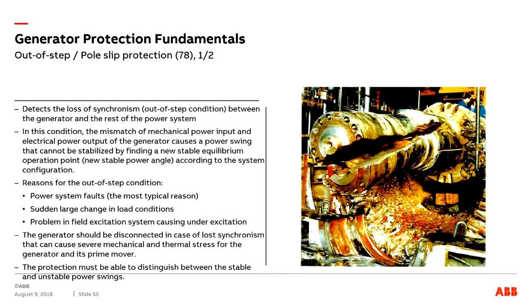The reason for an out of step condition could be power system faults, sudden large change in load conditions, or a problem in the field excitation system causing under excitation. Okay, the protection must be able to distinguish between stable and unstable power swings, which is important because there could be power swings in the system, and we should be able to detect which is unstable and which is stable.